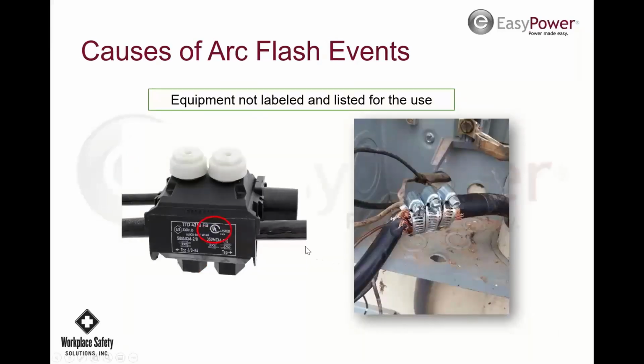Things need to be UL listed. So this is a UL listed splice. There's the UL marking. These clamps, if you look at the UL listing of these clamps, there's nothing that says anything about electrical connection. They're hose clamps. So, of course, the next thing the guy's going to do after he's got his 3 clamps on there is put about 15 layers of black tape. Then he's going to have his splice done.